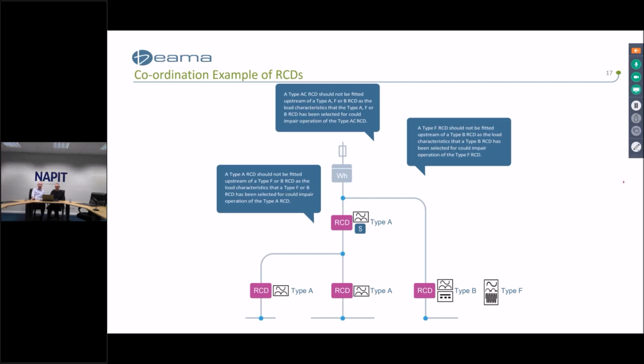Okay, so looking at coordination, and coordination of the types of RCD is actually very important, because if you have the wrong type of RCD downstream, it can affect an upstream RCD. So where a number of RCDs are used in the same installation, it's very important that this correct coordination is applied. Whenever RCDs are installed in series, the upstream RCD must be at least the same type, or what could be termed a higher type.